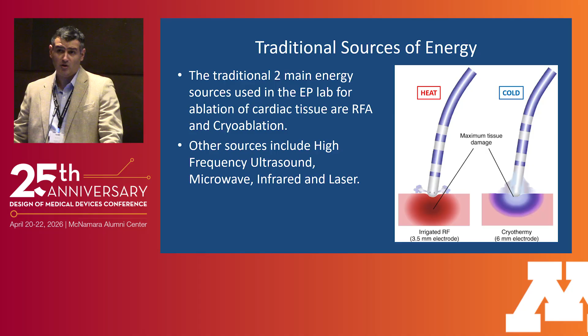The way you usually do cryo is you extract heat from the tissue by injecting a refrigerant through the catheter that you're using. The most common catheter that we used at first was this single tip catheter, which injects the nitrous refrigerant, and the nitrous refrigerant expands into the tip. When it expands, it absorbs a lot of energy, making the tip extremely cold. Then you apply it to the tissue, and by applying it, you kill the cells that you're intending to target. The full cryoablation lesion is a freeze, thaw, freeze sequence. If you freeze and you stop and say we're done, we have an effect, there's a good chance that the damage you did is reversible and the tissue is going to recover. So the full sequence is really freeze, thaw, freeze.